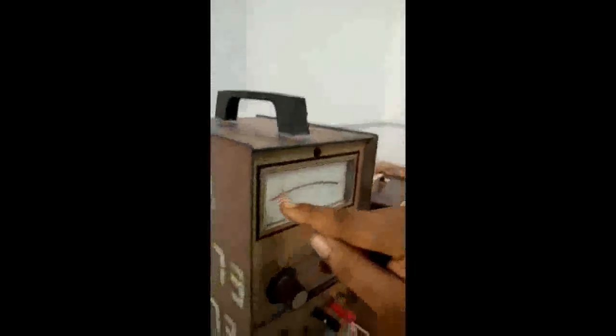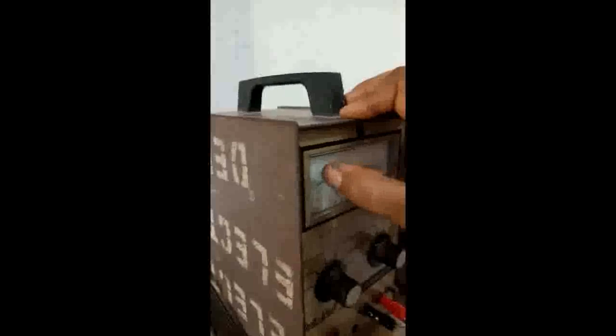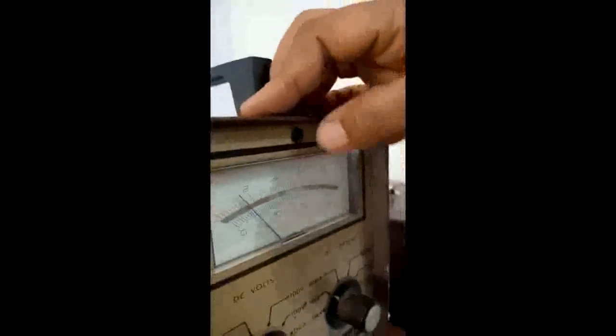You can see the upper scale ranges from 0 to 10. Because this has been set to 1 milliamp, the upper scale is not up to 10 again. Everything will be converted to 1 milliamp. Instead of having 1 here, it will be 0.1, 0.2, 0.3, 0.4 to 1. The reading of this one now, you can see from here to here is 0.1. We have 0.15. That's the reading of the current from the ammeter.